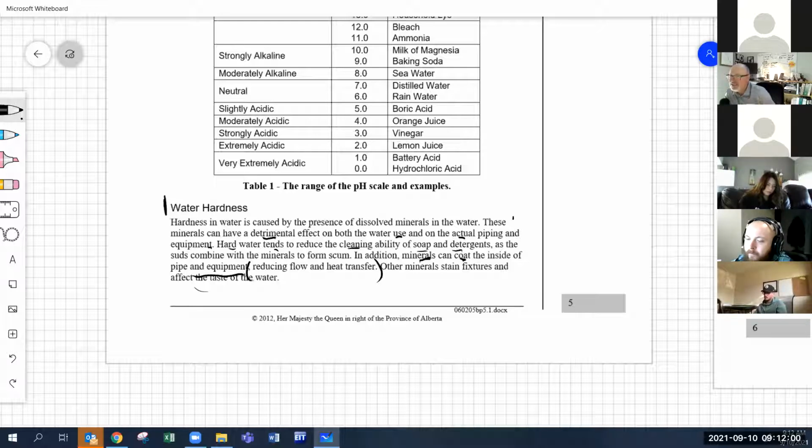Well, it's because that thing needs cleaned. The heat exchangers inside of these small flow-through boilers are made of very thin copper, right? Very thin copper. And if you put hard water through there, that copper will get coated on the inside, affecting the heat transfer to your water at the end use. So these boilers need to be serviced and cleaned constantly.